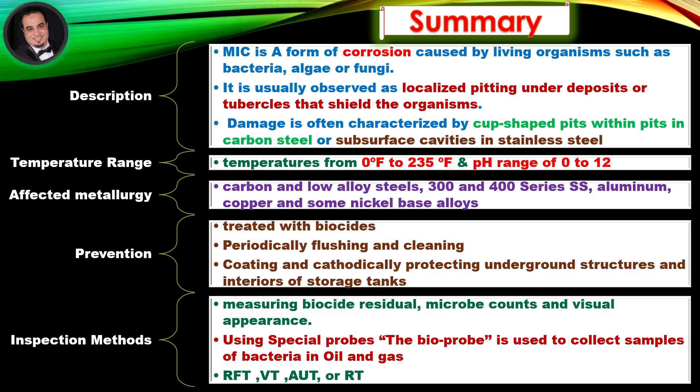Temperature range: 0°F to 235°F and pH range of 0 to 12. Affected metallurgy: carbon and low alloy steels, 300 and 400 series stainless steel, aluminum, copper, and some nickel base alloys. Prevention: treat with biocides, periodically flush and clean, coating and cathodically protect underground structures and interiors of storage tanks.